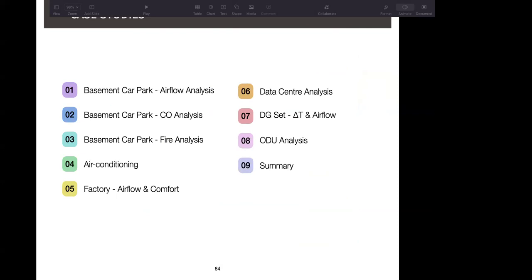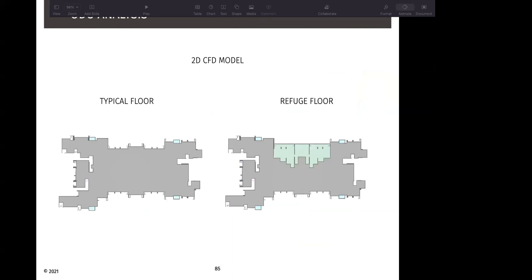And the last case study that I'd like to talk about is an ODU analysis, where we have a high-rise building with dedicated ODU shafts, where the ODUs are placed from say floor 0 to floor 50 or 60. If all the ODUs are considered to be working at 100% load, in tandem, will that heat affect the ODUs on the higher floors due to thermal stacking? Because the heat within the system will increase and flow upwards due to thermal stacking, it may get pulled in by the higher level ODUs on the intake side and then derate the ODUs. So we need to study the same.